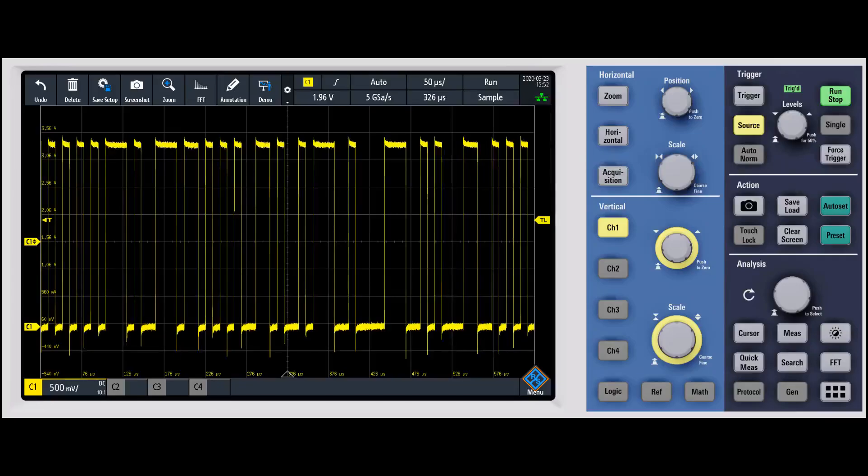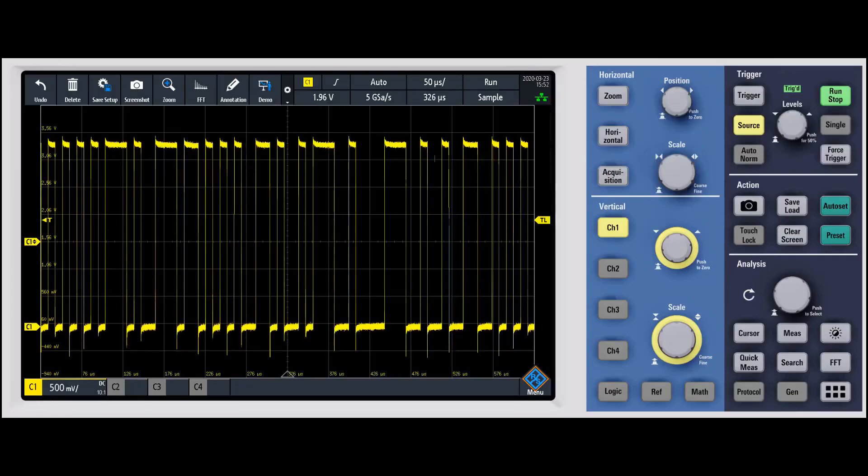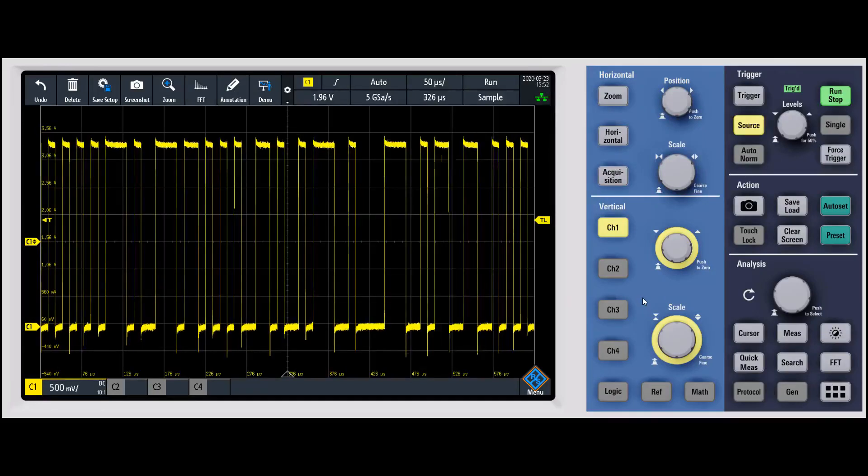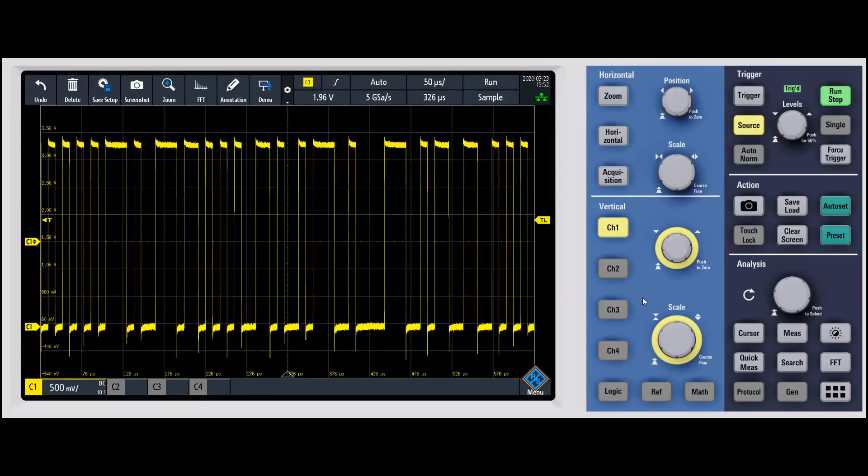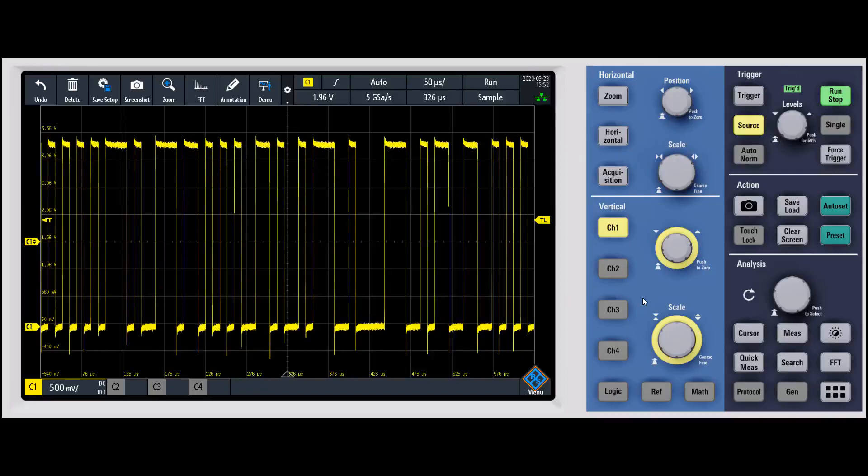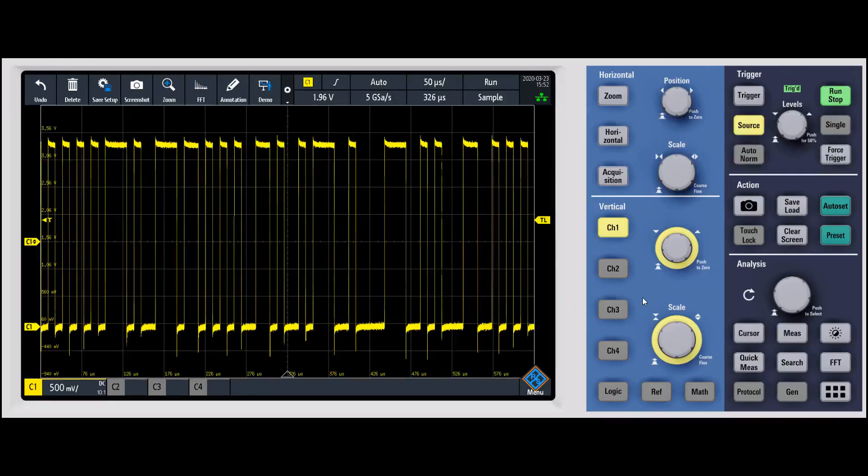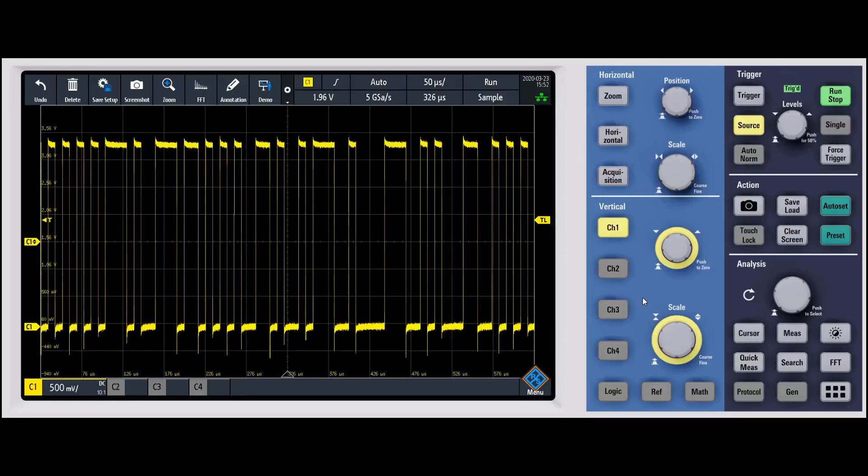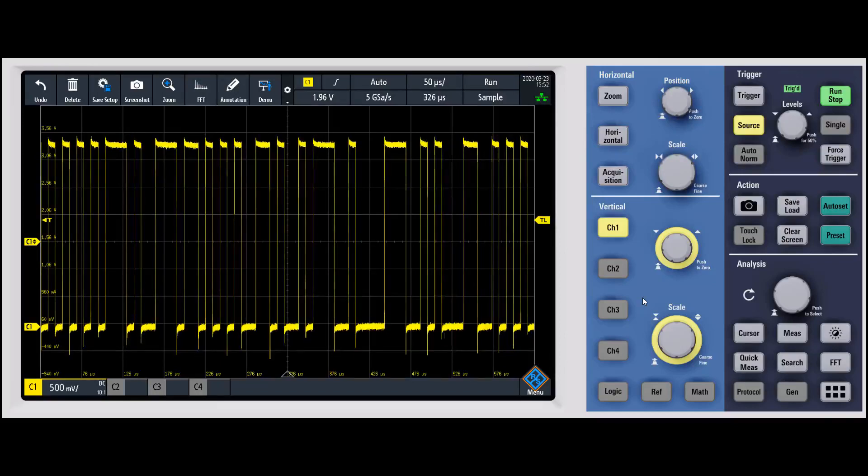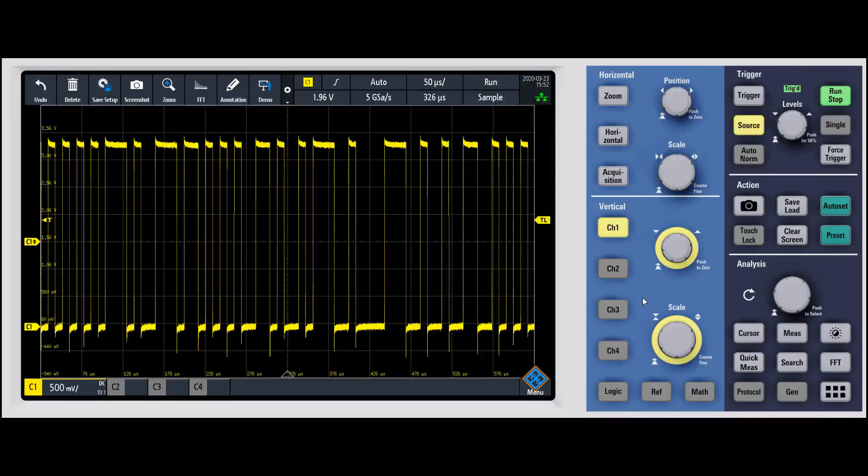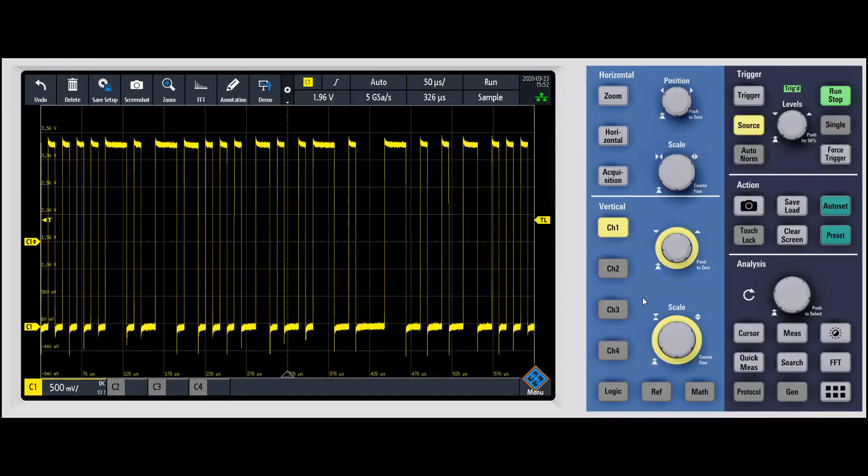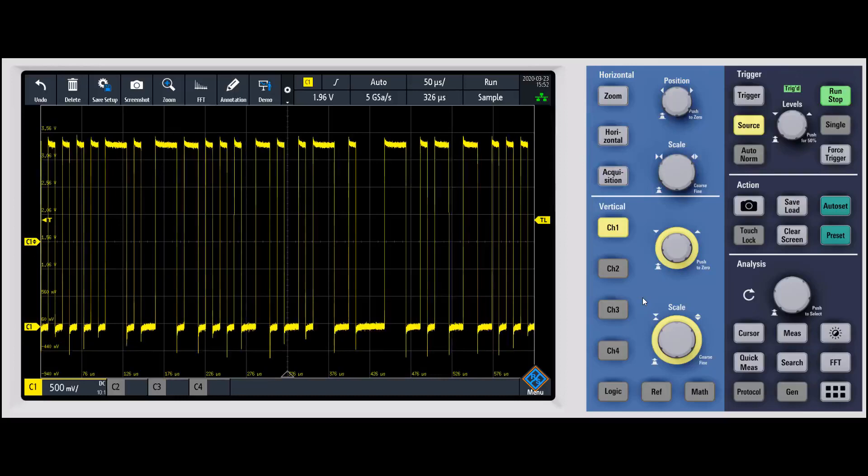In this video we're going to talk about high resolution mode. High res mode is a pretty common acquisition mode in oscilloscopes and what it does is basically take and do a boxcar averaging. It assumes that your sample rate is lower than the maximum sample rate, takes those extra samples that you have from the ADC, and averages those points into a single point. It'll take as many points as you have available depending on what your sample rate is.